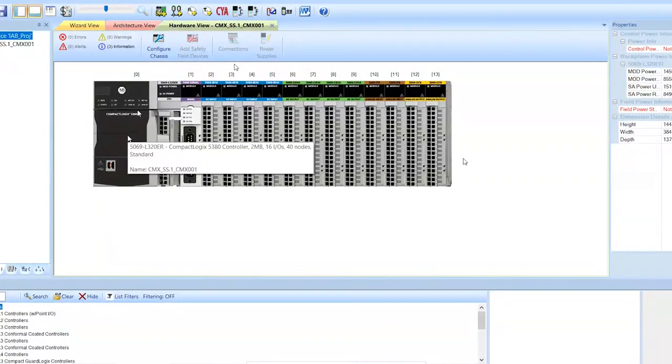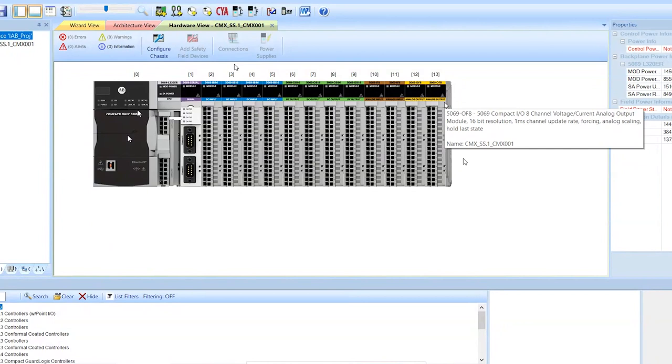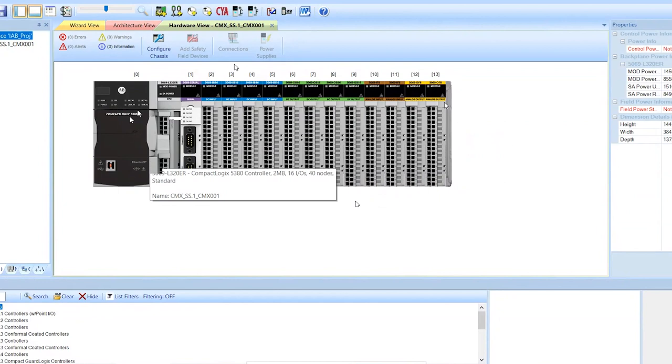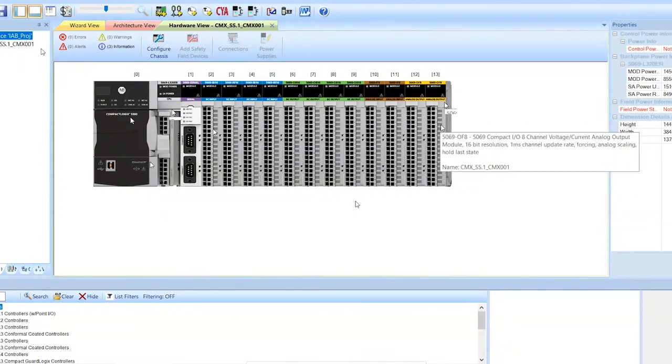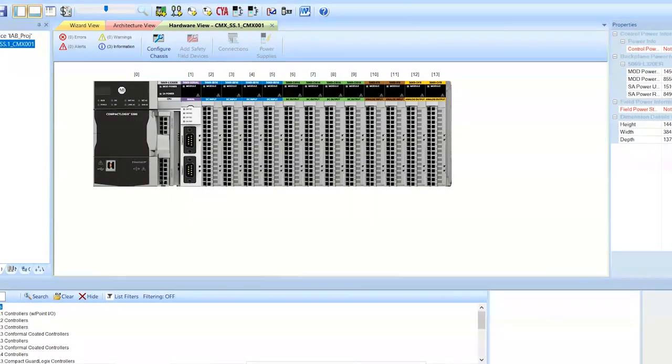The good thing with that is if you've manually gone through a system and you manually select a processor, say you select it based on memory, you've selected a 306 processor and you've selected 13 cards. You buy all that stuff and then you put it together. And then when you're testing, you realize that the 306 doesn't support 13 cards. Using this product will actually find that out right at the get-go. It'll tell you straight away, hey, you need a 320 to support the number of cards you've selected. It's very smart. It doesn't let you get away with these little errors that are very common when you're manually selecting and going through manuals.